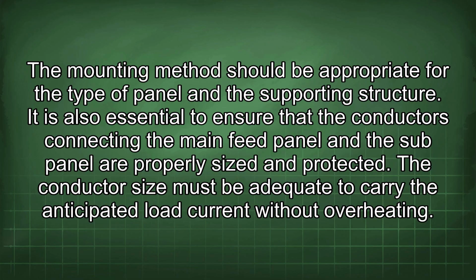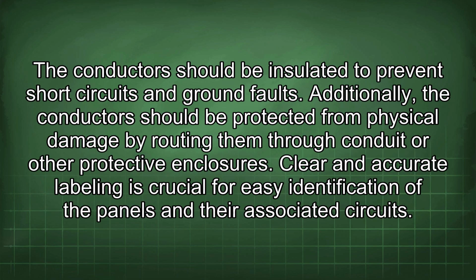It is also essential to ensure that the conductors connecting the main feed panel and the sub-panel are properly sized and protected. The conductor size must be adequate to carry the anticipated load current without overheating. The conductors should be insulated to prevent short circuits and ground faults. Additionally, the conductors should be protected from physical damage by routing them through conduit or other protective enclosures.